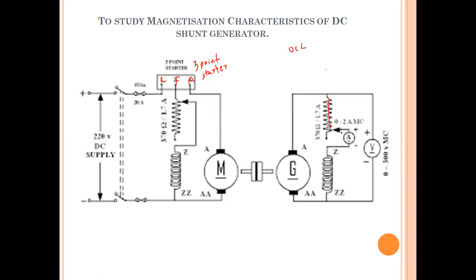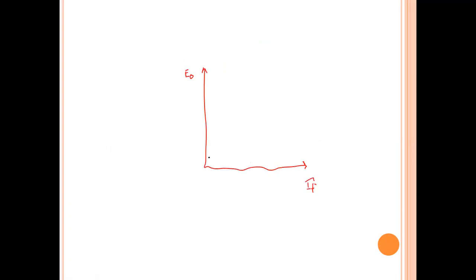Regarding voltage buildup in a generator: initially, there is residual flux present in the field winding. When the armature of the generator rotates, it cuts that residual flux and an EMF is induced. So when the field current is zero, there is still a small value of EMF induced, which is called the residual EMF.